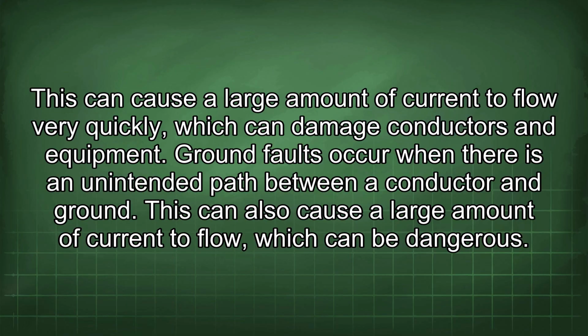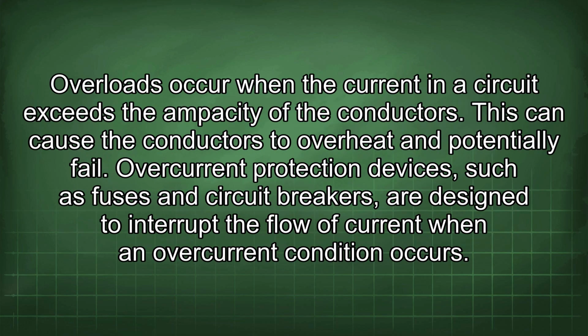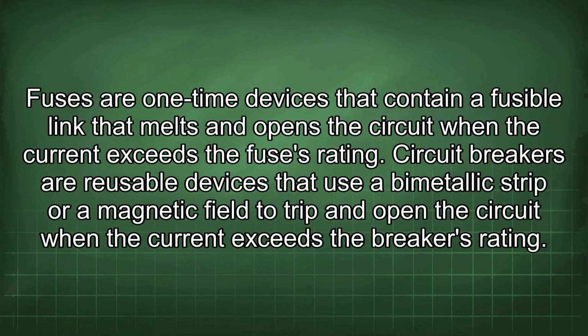Ground faults occur when there is an unintended path between a conductor and ground. This can also cause a large amount of current to flow, which can be dangerous. Overloads occur when the current in a circuit exceeds the ampacity of the conductors. This can cause the conductors to overheat and potentially fail. Overcurrent protection devices, such as fuses and circuit breakers, are designed to interrupt the flow of current when an overcurrent condition occurs. Fuses are one-time devices that contain a fusible link that melts and opens the circuit when the current exceeds the fuse's rating. Circuit breakers are reusable devices that use a bimetallic strip or a magnetic field to trip and open the circuit when the current exceeds the breaker's rating.